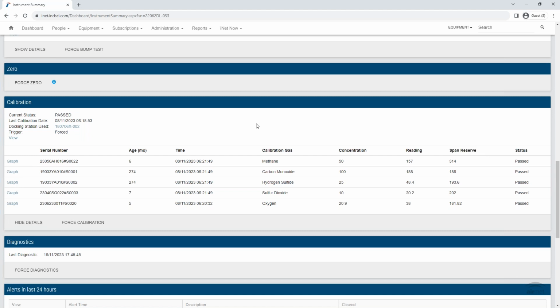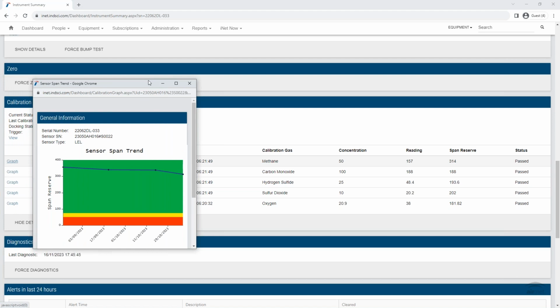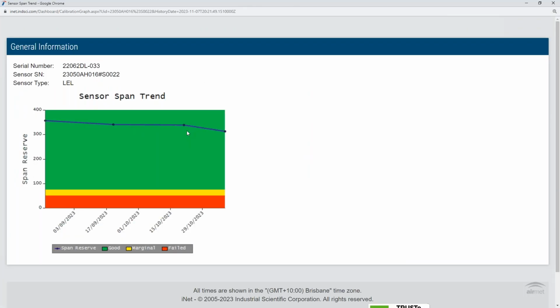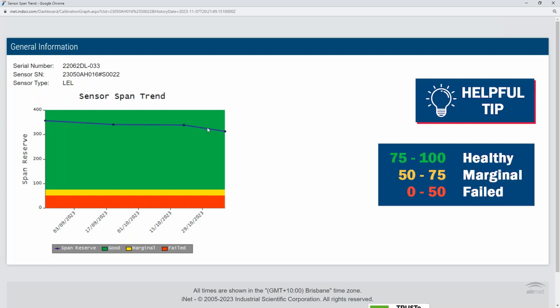To view a graphical representation of the sensor's health, click on Graph, which is located to the left of the sensor. This will show a graph of all of the calibration results of the LEL sensor. If the span reserve, as shown here in this blue line, is within the green range, the sensor is healthy and works as intended. If the span reserve indicates 75 or below, the sensor is marginal. This indicates that it still works as intended, but may be reaching the end of its life and would be replaced soon. If the sensor has failed, or is 50 or below, the sensor should be replaced immediately to ensure the gas detector continues to work reliably and accurately.